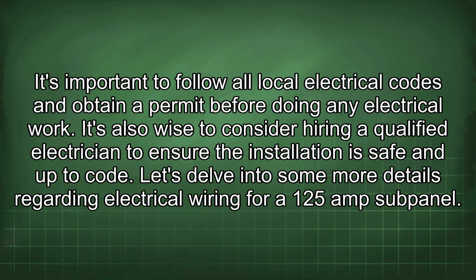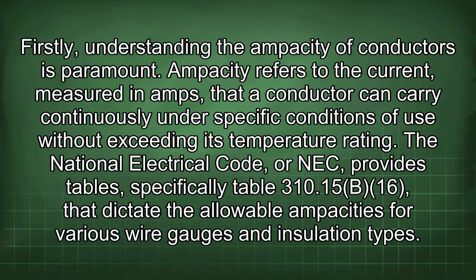Let's delve into some more details regarding electrical wiring for a 125 amp subpanel. Firstly, understanding the ampacity of conductors is paramount. Ampacity refers to the current, measured in amps, that a conductor can carry continuously under specific conditions of use without exceeding its temperature rating. The National Electrical Code, or NEC, provides tables, specifically Table 310.15(B)(16), that dictate the allowable ampacities for various wire gauges and insulation types.